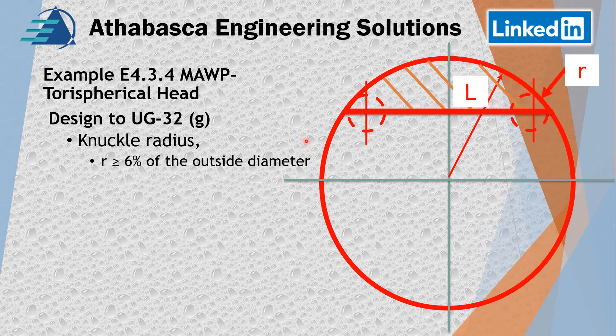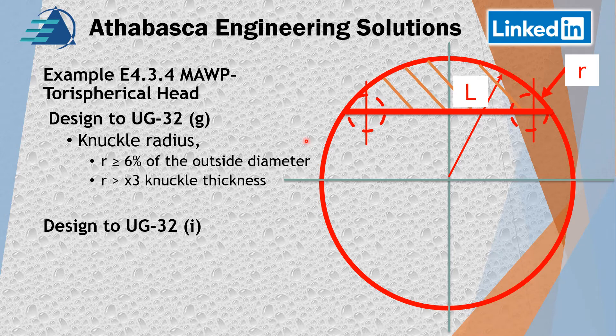The code states that R has to be greater than or equal to 6% of the outside diameter of the vessel to which the head is attached. Then it says R has to be at least three times greater than the knuckle thickness. Those are the basic rules. If you follow those, then you can follow all the Division 1 rules, and it's a lot simpler.